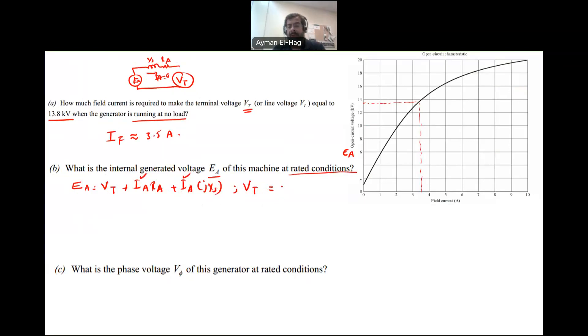Vt is the terminal voltage for single phase. Since the generator is Y connection, it's 13.8 kV divided by root 3, which equals 7.967 angle 0 kV. Ia is the armature current or phase current. For Y connection, the phase current equals the line current, so it's S divided by root 3 times 13.8 kV, which gives 2092 amps.